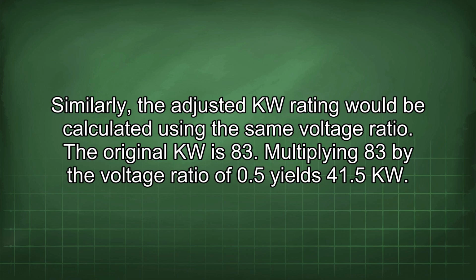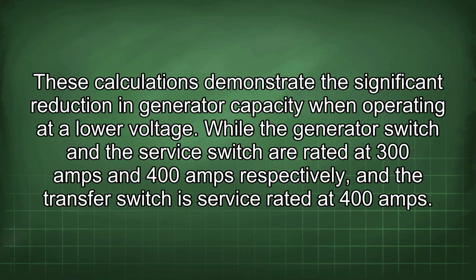Similarly, the adjusted KW rating would be calculated using the same voltage ratio. The original KW is 83. Multiplying 83 by the voltage ratio of 0.5 yields 41.5 kW. These calculations demonstrate the significant reduction in generator capacity when operating at a lower voltage.